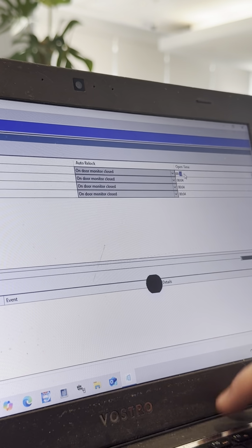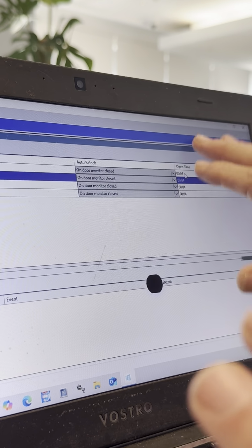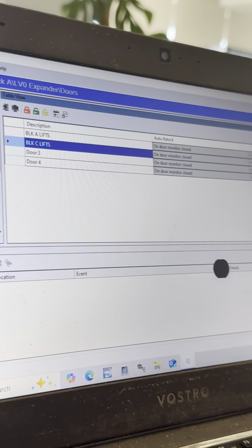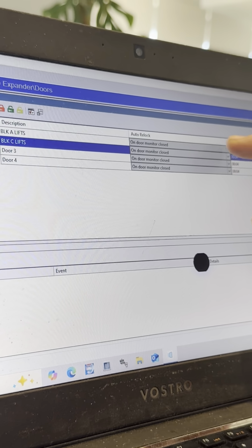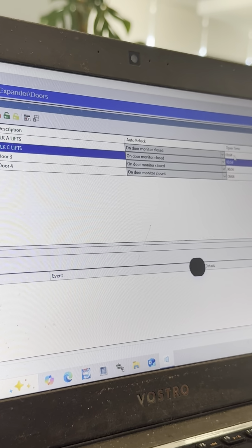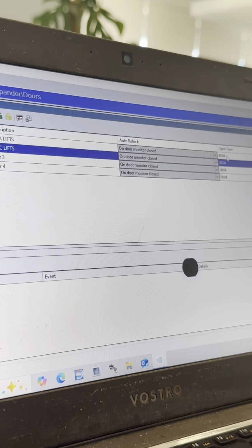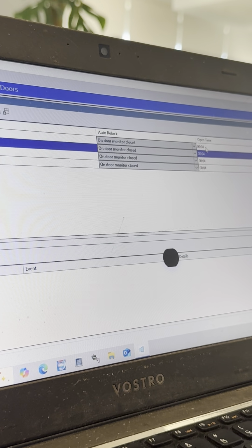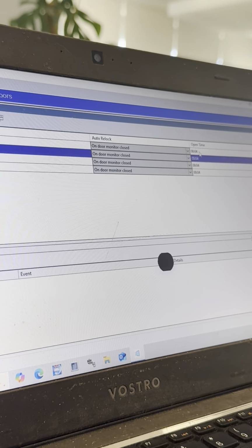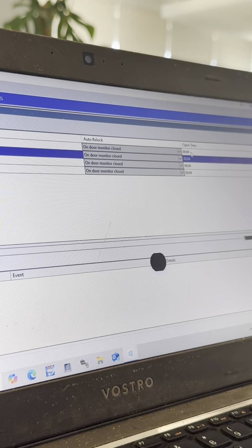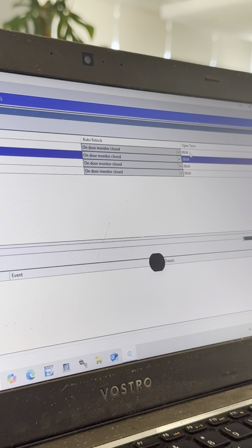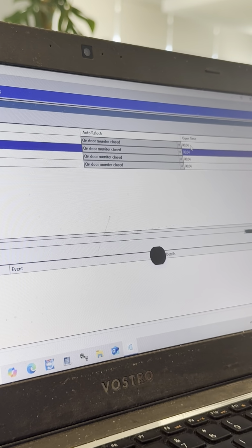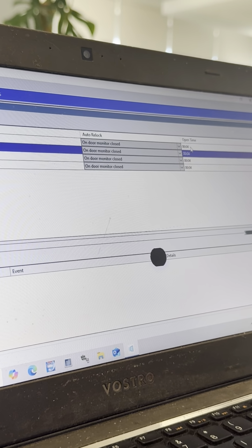So we'll just do that as 04, put it back. So that basically is your time of how long the lock stays open. When it comes down to a magnet, you can do whatever you want, or a fail-safe lock. If this is a striker, do not go high, because you will burn the striker. Unless it's fail-safe. If it's fail-safe, it's like a magnet, so it always has power, so it's always burning. And when you take off power, you can do it anytime. You can do it for an hour, no problem. But you can't have a striker applying power for an hour. This will burn the coil. Not an hour, not even a minute, because you'll burn the coil. I would say even 10 seconds is pushing it, to be honest, for a striker.